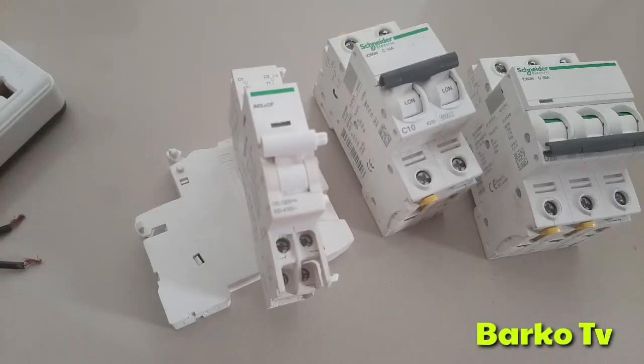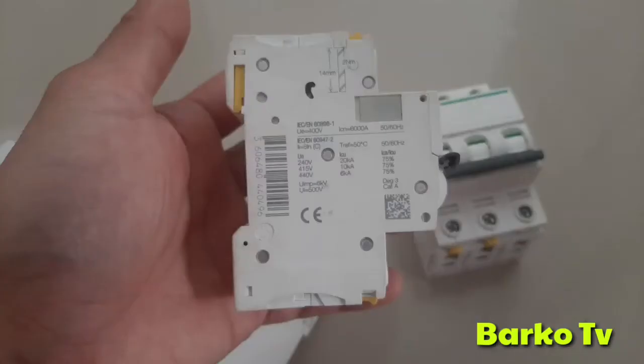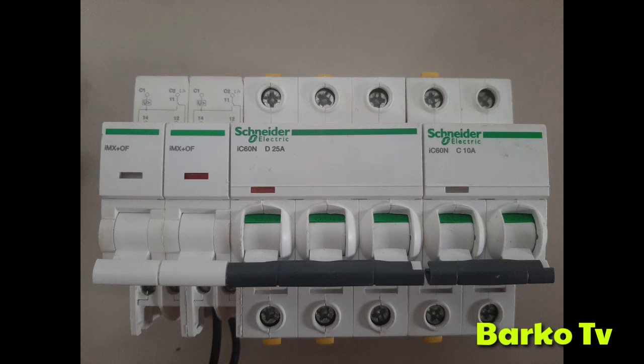We'll do a recap first. This shunt trip is used in our ship commonly in the preferential trip, preferential trip number 2, PT1 and PT2, CO2-1, CO2-2. It depends upon the usage, because sometimes the circuit breakers supply the fans, we need to shut it down in case of fire. Also, emergency stop 1, emergency stop 2, it depends upon the location.